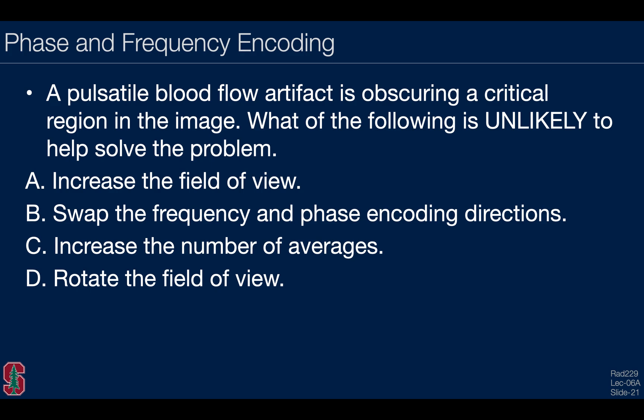Quick quiz, a pulsatile blood flow artifact is obscuring a critical region in the image. One of the following is unlikely to help solve the problem. You can pause the video while you think about this and look through the answers and I'll proceed in a second to discuss this. We could increase the field of view and that would give us more space around the object, but that seems unlikely to do anything specifically with regards to blood flow artifacts. Whereas we've seen that swapping the frequency and phase encode directions could push the artifact into a region of relative uninterest so that it overlaps with something that's not of relevance to the observation or measurement that needs to be made. We know that we could increase the number of averages and through signal averaging, we can push down incoherent artifacts. And it may, in fact, actually help to rotate the field of view slightly. So rather than swapping phase and frequency, sometimes just rotating by 10 or 30 degrees is sufficient. In this case, I would say increasing the field of view is not going to specifically help.